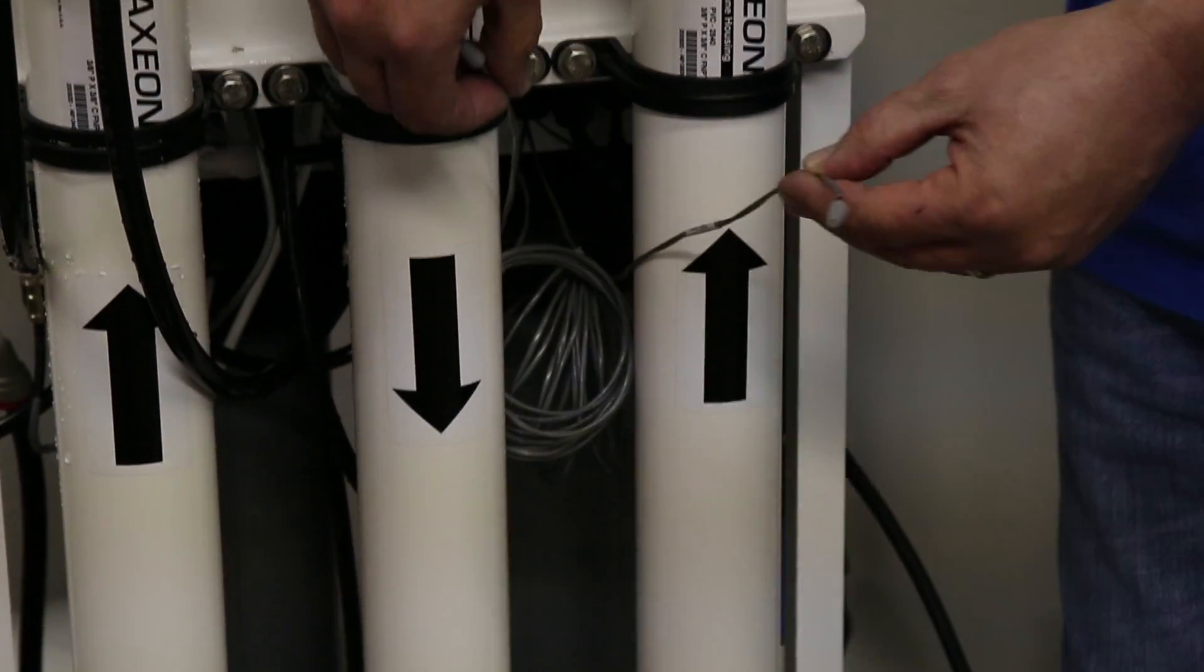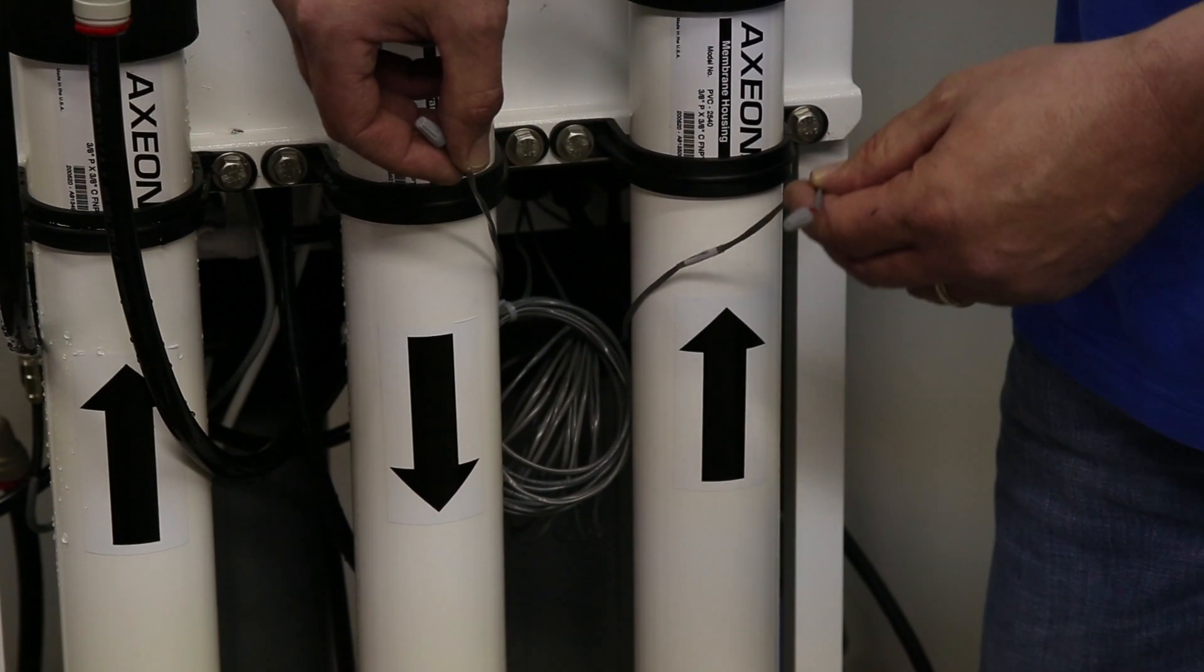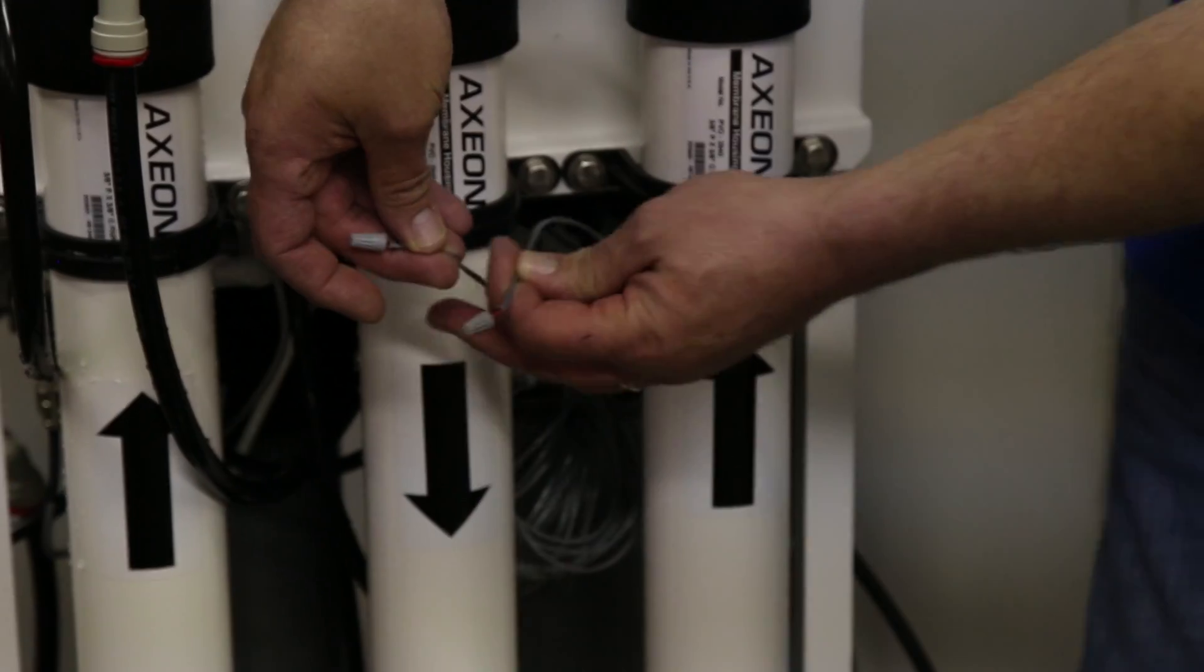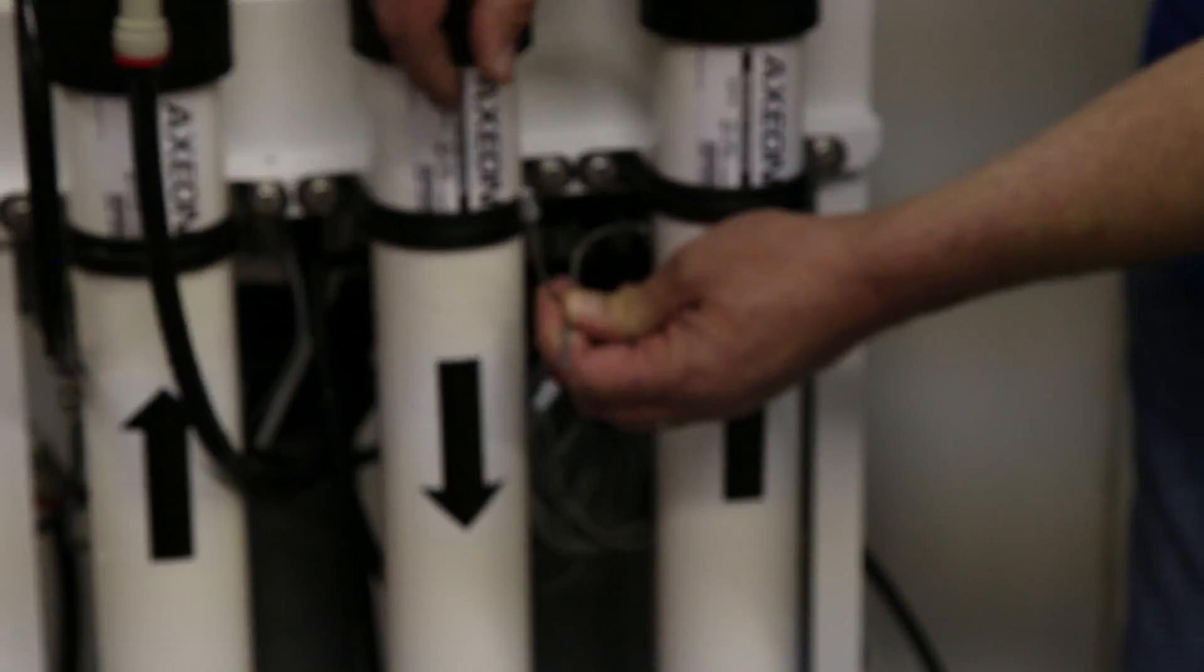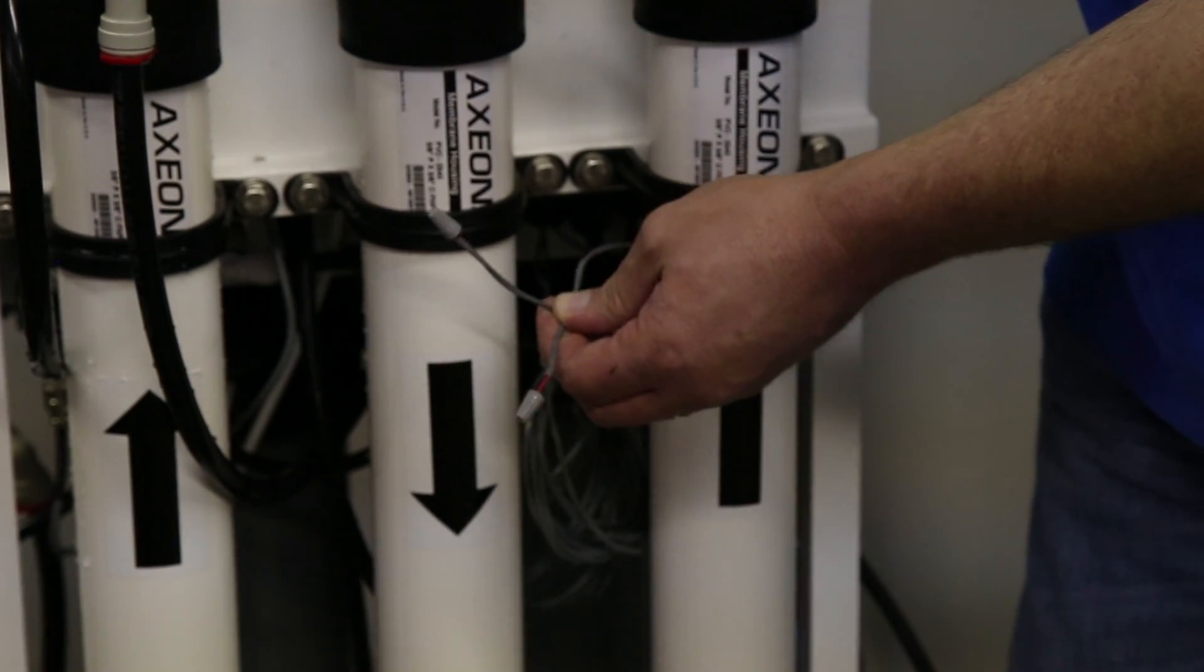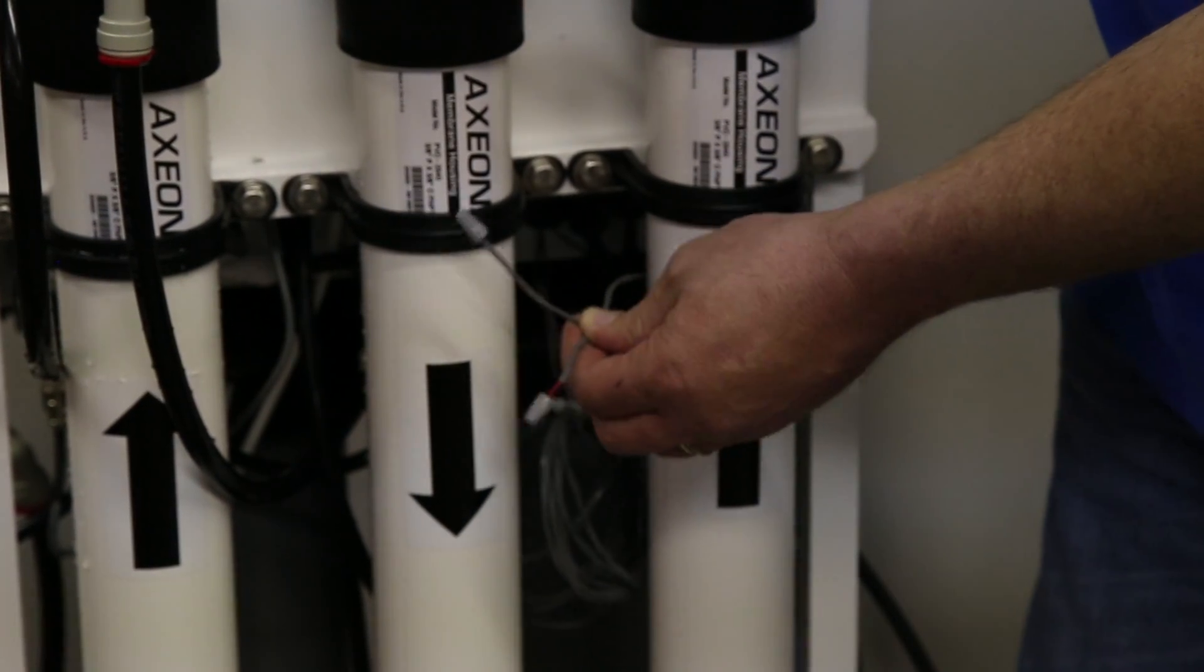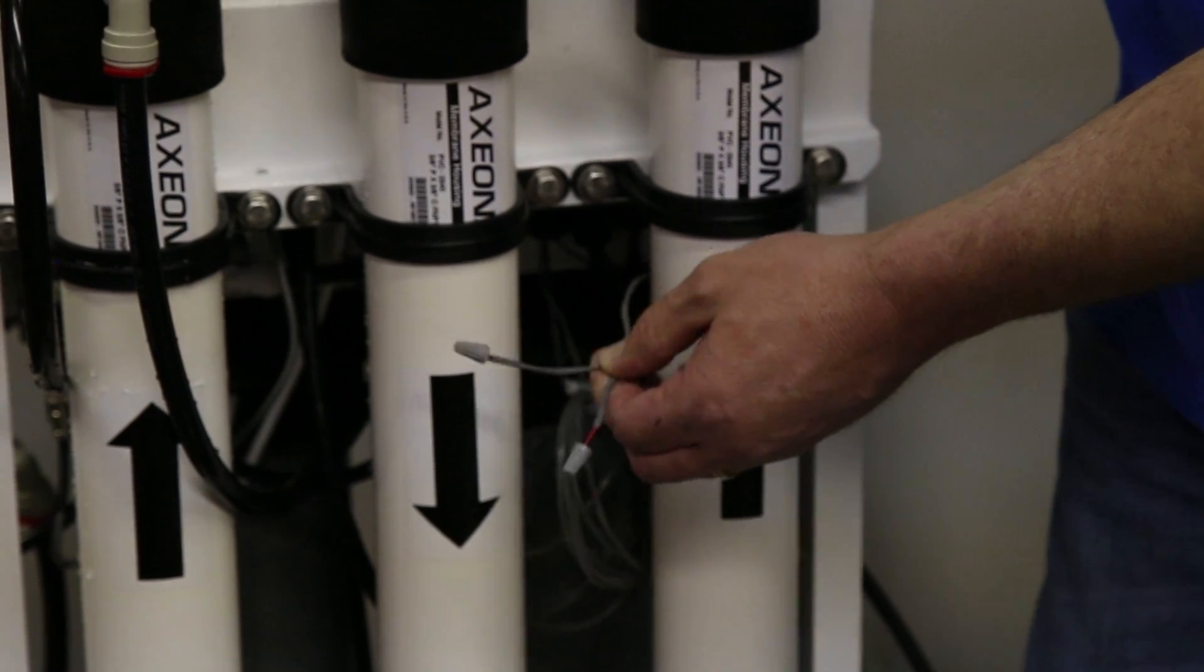These are actually control circuits to turn the RO on and off. They are no voltage switch closure circuits. So you don't want to put voltage to them or you'll actually damage the board in the controller.